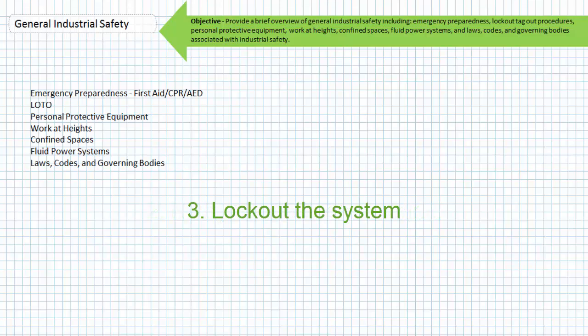Step 3: Lockout, release, or block all sources of energy that have the potential to unexpectedly start, energize, or release during the course of the procedure. Step 4: Verify the system is isolated. Trust no one. Your life is on the line. Use your voltmeter to perform voltage checks. Read pressure gauges. Look at the thermometer.